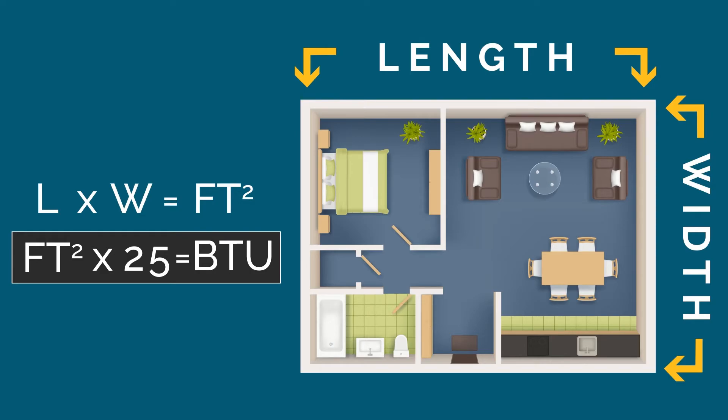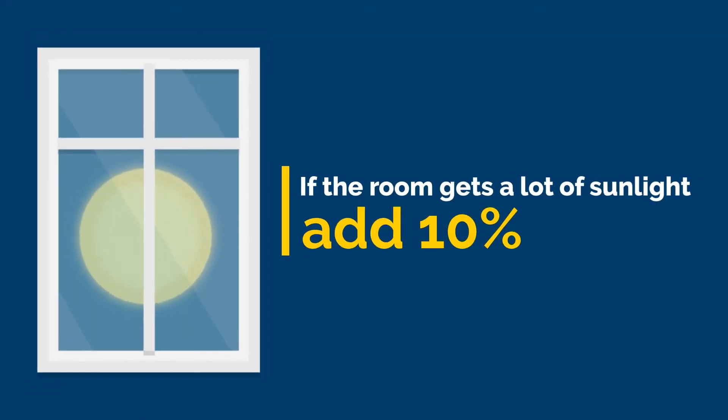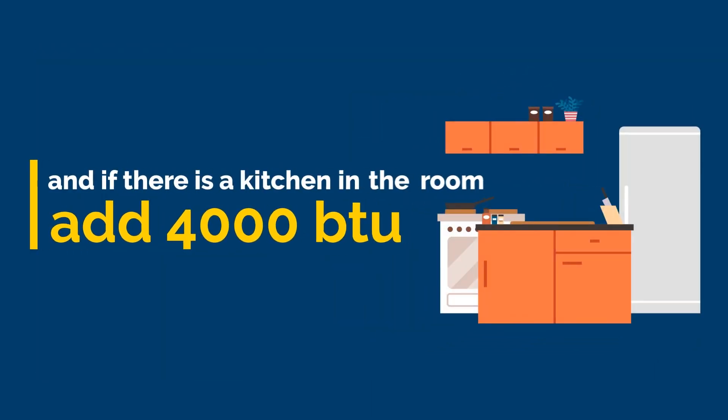Now take into consideration: if the room gets a lot of sunlight, add 10%; and if there is a kitchen in the room, add 4000 BTU.